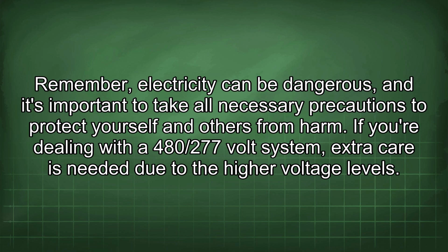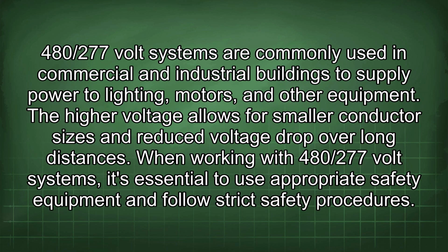If you're dealing with a 480/277 volt system, extra care is needed due to the higher voltage levels. 480/277 volt systems are commonly used in commercial and industrial buildings to supply power to lighting, motors, and other equipment. The higher voltage allows for smaller conductor sizes and reduced voltage drop over long distances.